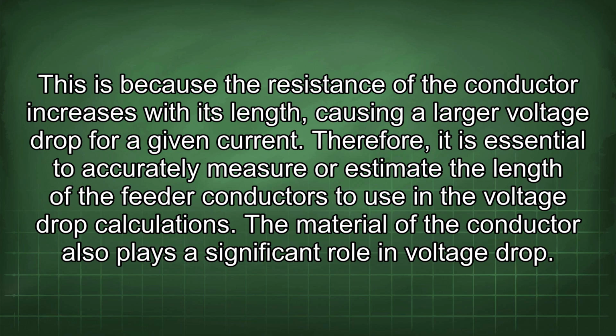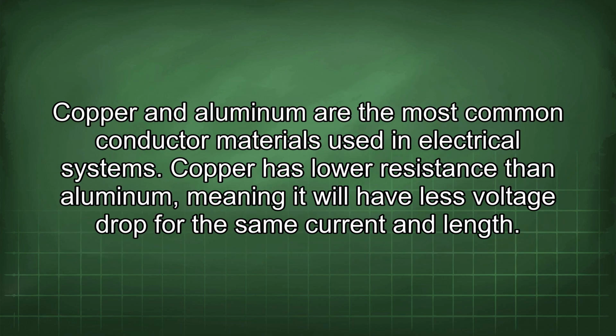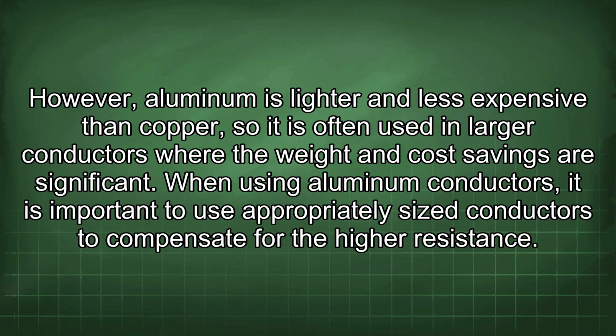voltage drop calculations. The material of the conductor also plays a significant role in voltage drop. Copper and aluminum are the most common conductor materials used in electrical systems. Copper has lower resistance than aluminum, meaning it will have less voltage drop for the same current and length. However, aluminum is lighter and less expensive than copper, so it is often used in larger conductors where the weight and cost savings are significant. When using aluminum conductors, it is important to use appropriately sized conductors to compensate for the higher resistance.